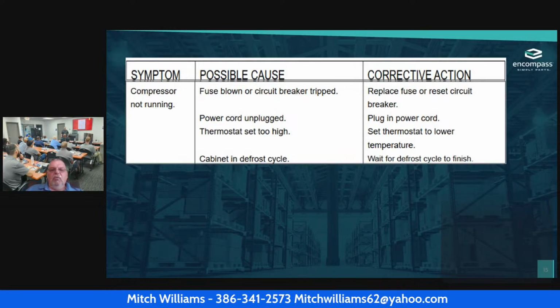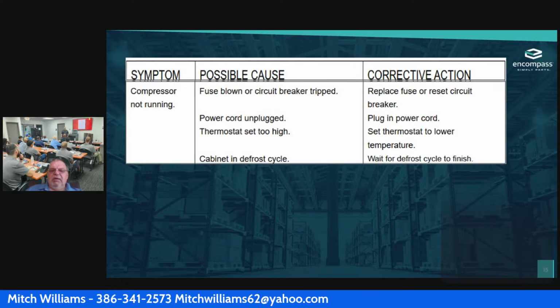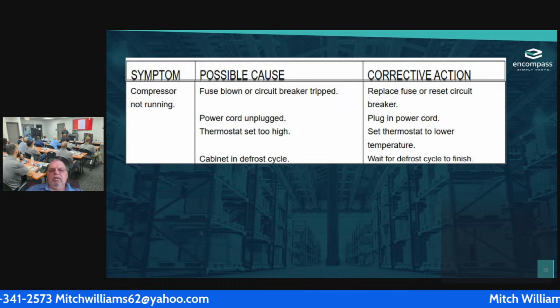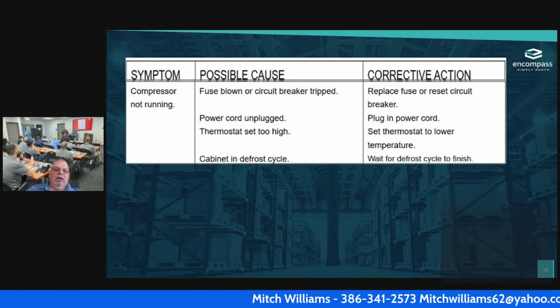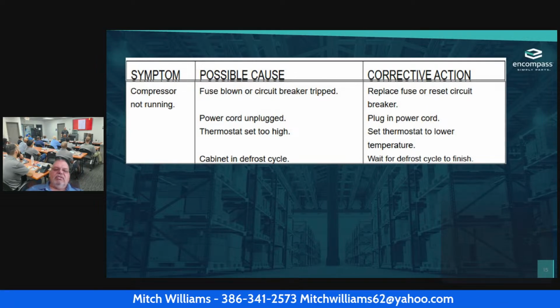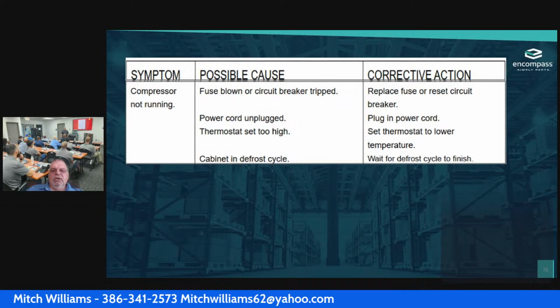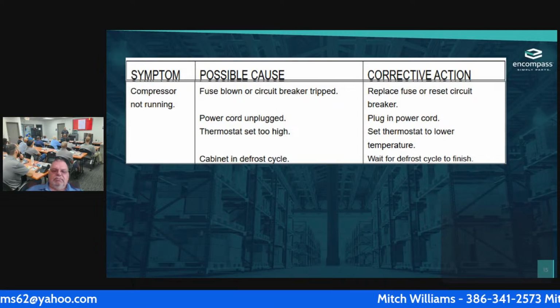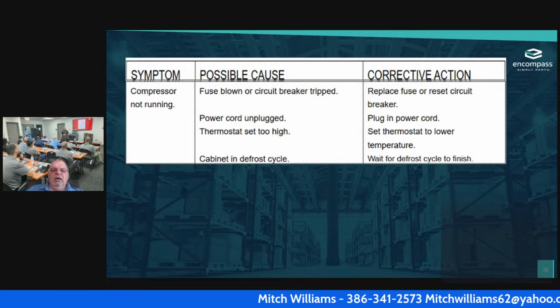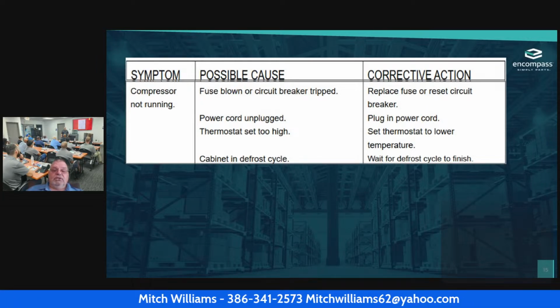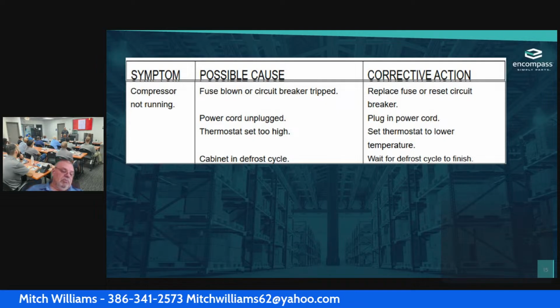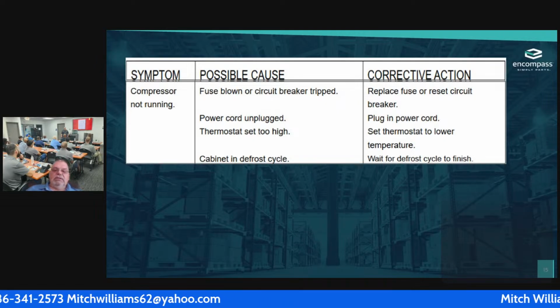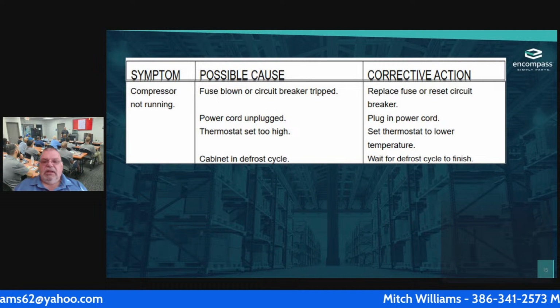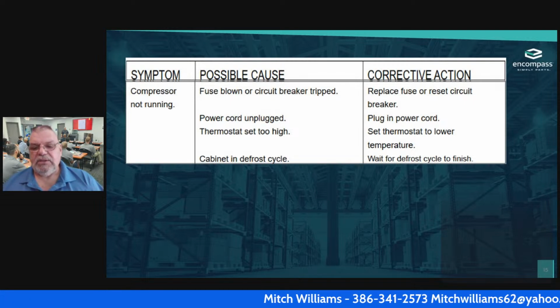Okay. One of the other things I'm going to check is to make sure that the power cord is plugged in correctly. I'm going to measure the voltage to the power cord to make sure that it's right. One of the other things that it can be is that the thermostat is set too high. So if I find that out, I'm going to have to set the thermostat to a lower temperature. Then it could be that the cabinet is in the defrost cycle. So I'm going to have to either wait for it to finish, or I'm going to tell the customer that, hey, this unit's in a defrost cycle. That's what your problem is.